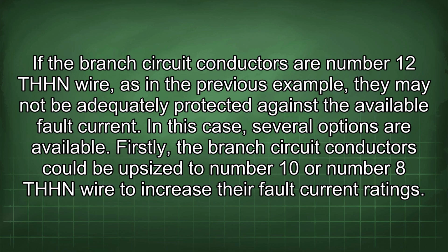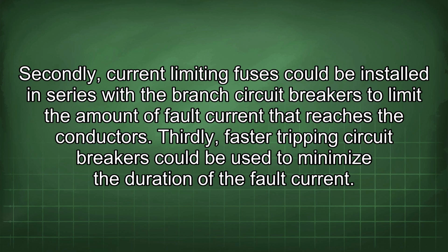In this case, several options are available. Firstly, the branch circuit conductors could be upsized to number 10 or number 8 THHN wire to increase their fault current ratings. Secondly, current limiting fuses could be installed in series with the branch circuit breakers to limit the amount of fault current that reaches the conductors. Thirdly, faster tripping circuit breakers could be used to minimize the duration of the fault current.